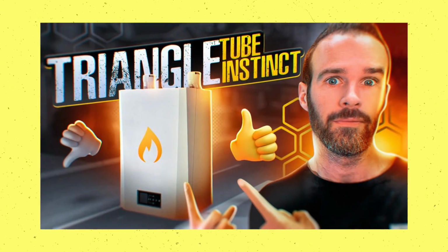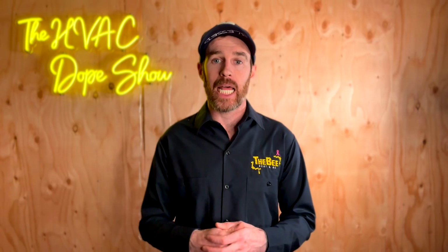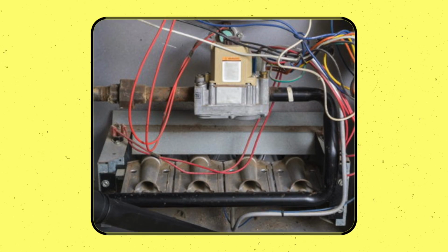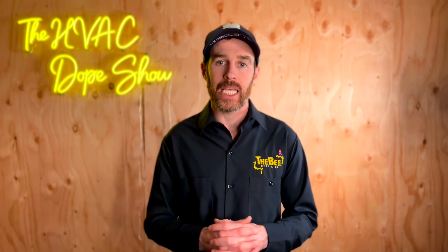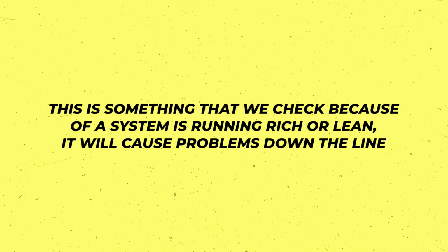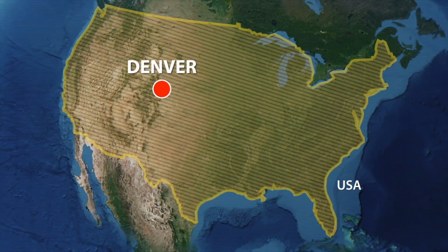And there's a video we put out about the Triangle Tube Instinct combi boiler a few months back, and I put a combustion analyzer in the boiler to showcase its efficiency. And with modulating systems like that, you're basically just doing it as a check because you have an electronically modulating gas valve that is doing all of the tuning for you. Single stage systems, on the other hand, you'll need to tune by hand by adjusting the gas valve. And the bottom line is that this is something that we check because if a system is running rich or lean, it will cause problems down the line, and it's just something we do to make sure that the system is running well.